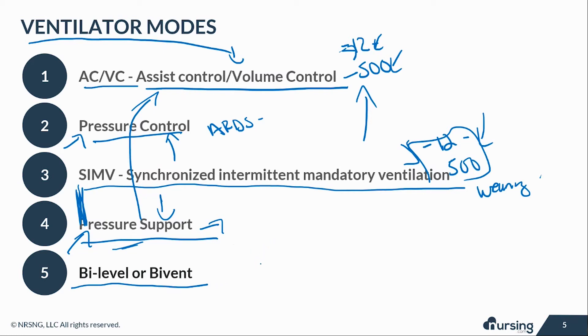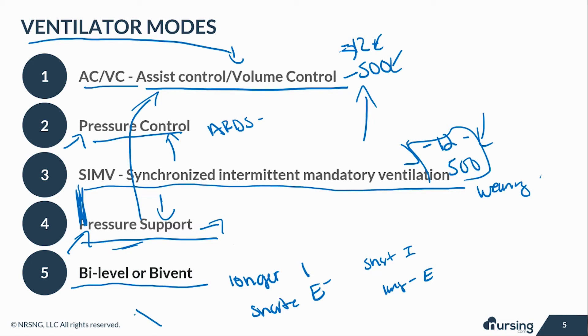Lastly, there is a bi-level or bi-vent mode. This is typically used when a conventional vent is no longer working for a patient, as it is more advanced and not all ventilators support it. It has high and low settings, and allows you to set longer inspiration with shorter expiration, or shorter inspiration with longer expiration. This helps patients with oxygenation problems where the conventional vent is just not doing the work.